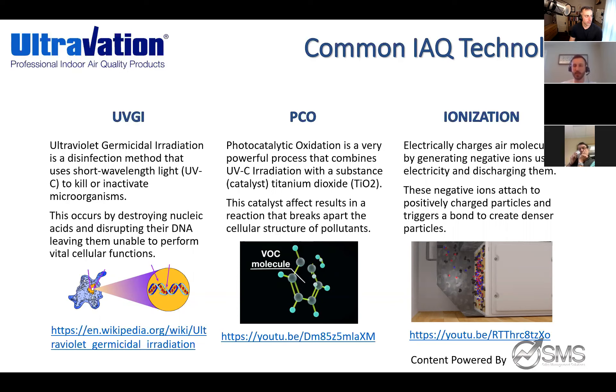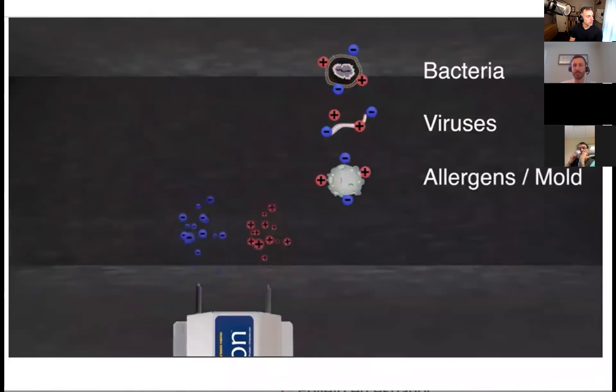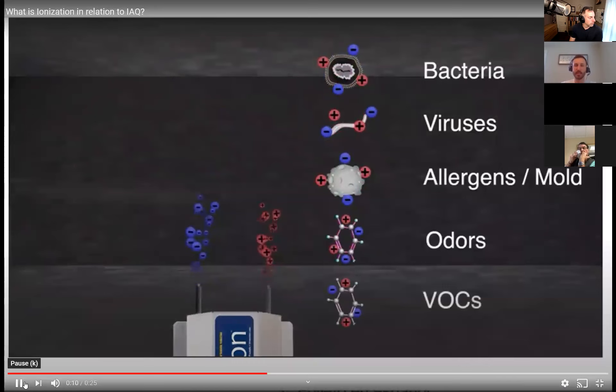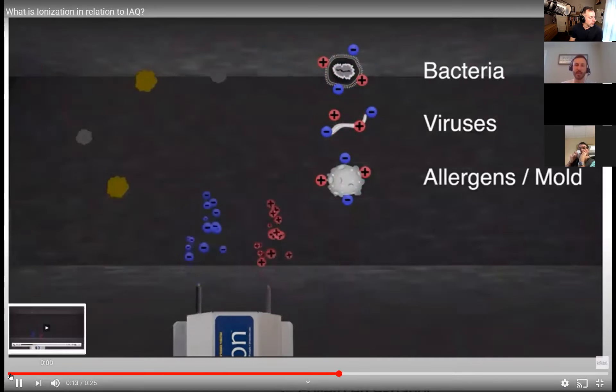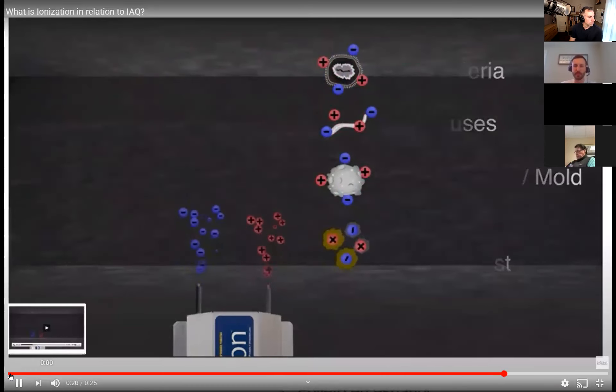Ionization is the other common IAQ technology. You mount this right before your air filter. When ionization is taking place, it's electrically charging air molecules by generating negative ions and discharging them. These negative ions attach to positively charged particles and trigger a bond to create denser particles — basically taking any filter, whether a one-inch, MERV-11, or MERV-13 filter, and enhancing it. It clumps up bacteria, viruses, allergens, molds, odors, and VOCs, making them bigger and allowing them to be caught in your air filter a lot better.